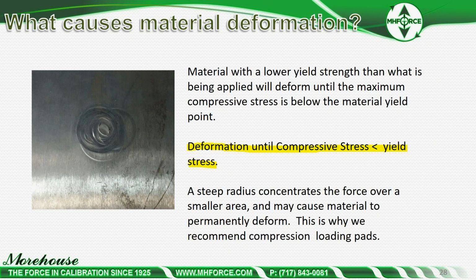That's why we have them. That's why we recommend people have them. Top blocks, hardened top blocks, all types of different blocks. Just use the same material for your calibration that the load cell is calibrated with. You want to replicate those results.